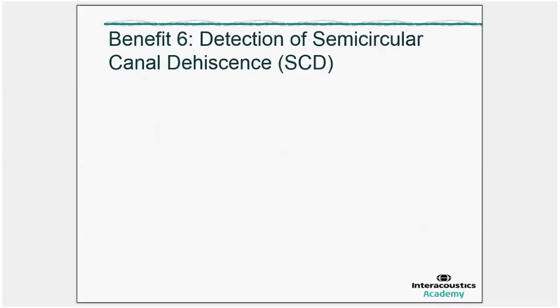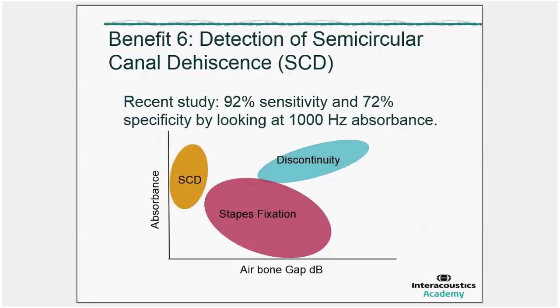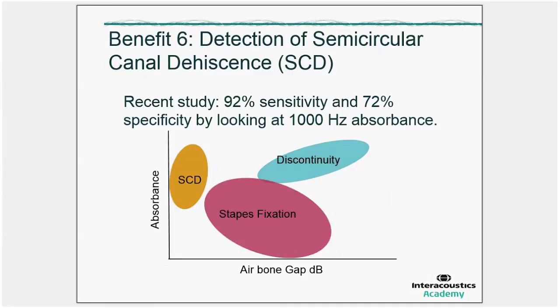Benefit number six. It's a completely different area. It's about the detection of semicircular canal dehiscence. There is a recent study done by Heidi Nakajima who indicates that by measuring absorbance, you can reach 92% sensitivity and 72% specificity for detecting semicircular canal dehiscence. And one of the graphs that she shared in one of her articles is the one shown here, which has the absorbance. The height of the absorbance as function of the air bone gap gives a very good indication if it's semicircular canal dehiscence or if it's maybe a fixation or discontinuity. We really hope to see more from Heidi Nakajima.